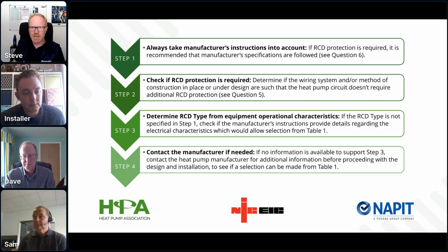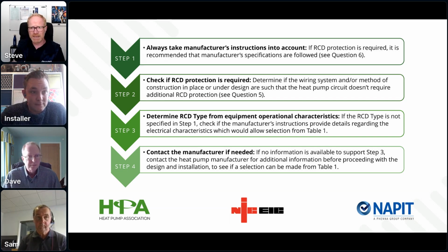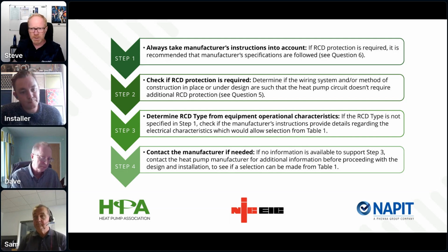That is actually true. So when we have additional requirements, those are intended for socket outlets and mobile equipment for use outdoors, and heat pumps don't apply in those circumstances. However, we do look at the selection of an RCD for a heat pump allowing for other equipment, and that is covered in the current regulations. So the most likely requirement to install an RCD is because of the type or installation method of the cable that's being used to supply the actual heat pump. Now that falls under regulation group 522.6, and device selection is covered also in part 5, which is 531.3. So there are references, but it's not specific to RCDs for heat pumps.